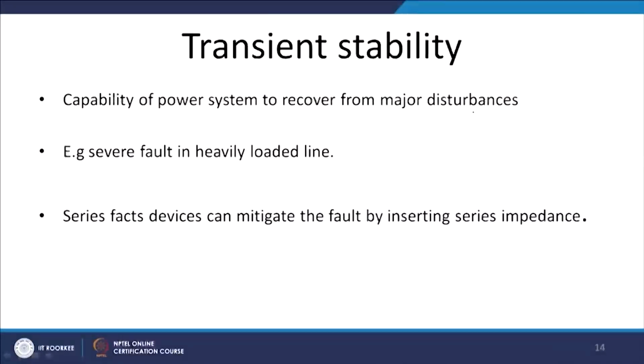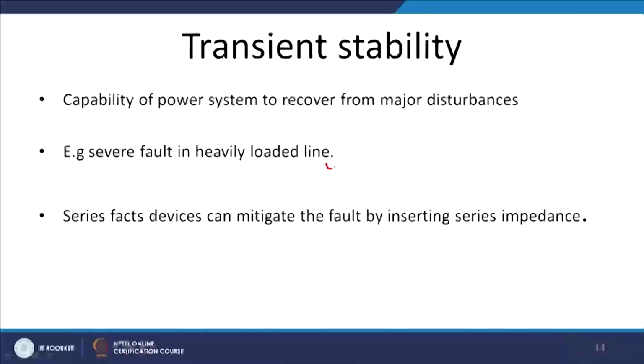Now, transient stability. An example of transient stability is when a loaded line has an LG fault or line to line fault, then all of a sudden there is a huge change in the dynamics of the power system. So, this is actually a severe fault in a heavily loaded line. Then a FACTS device can be used to mitigate this fault and increase the stability of the system. In the same way, dynamic stability: if the system has a power oscillation and thus the torque angle oscillates, we need to damp out that oscillation actively, and that is also possible with FACTS devices.